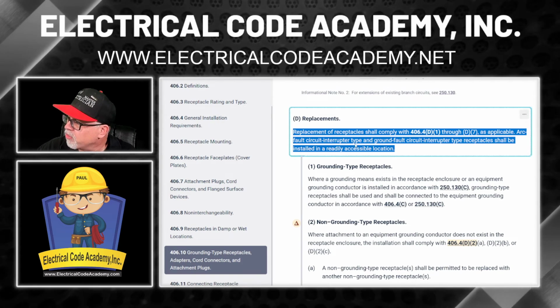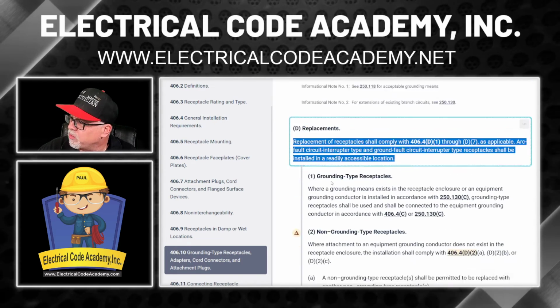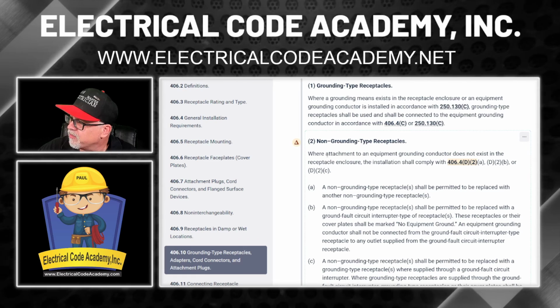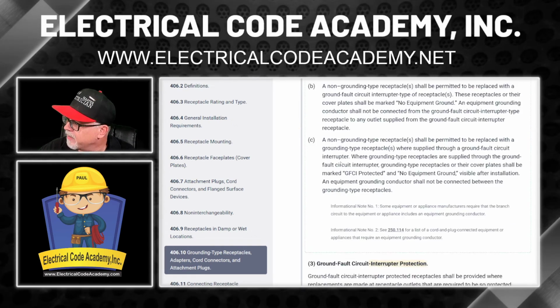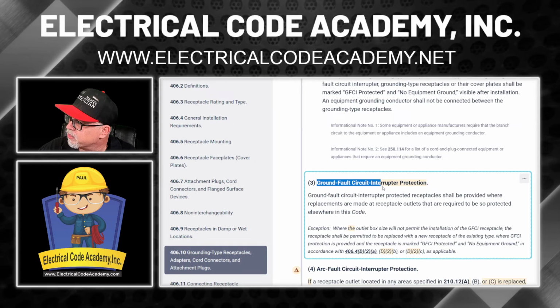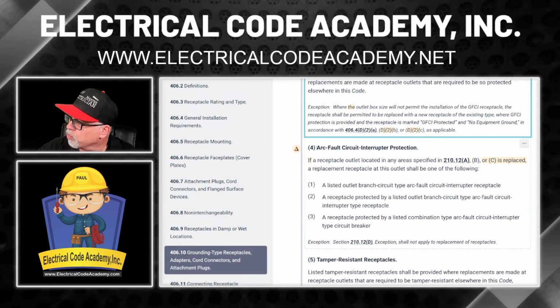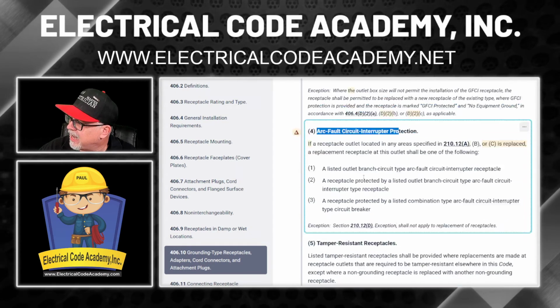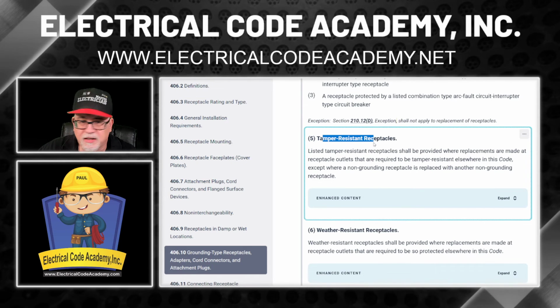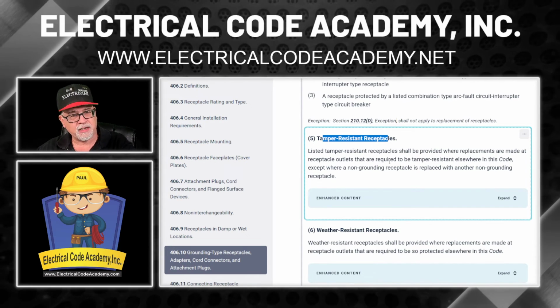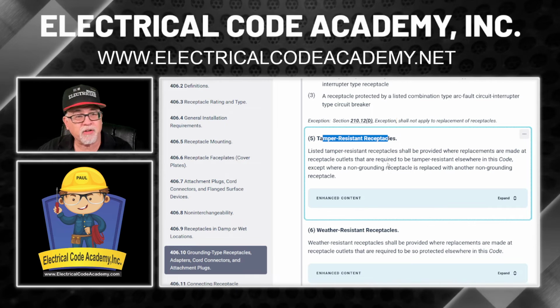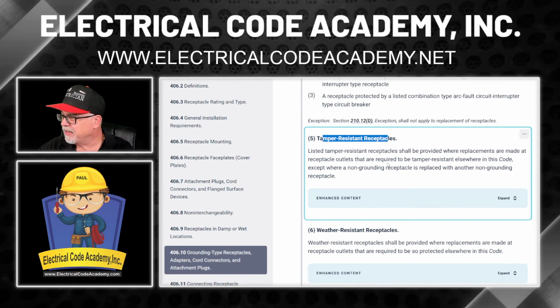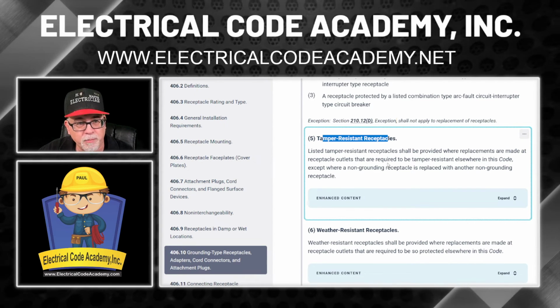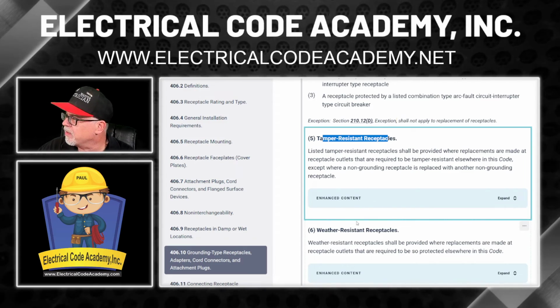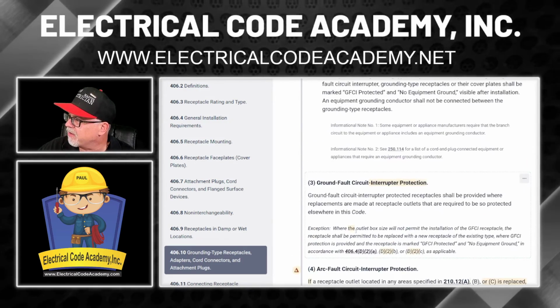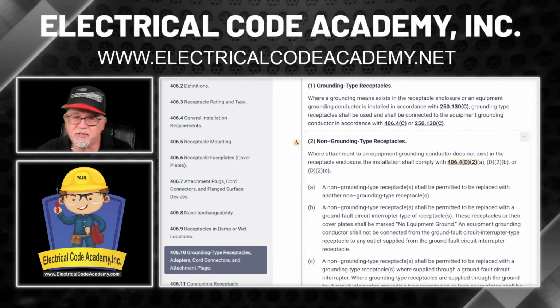Okay, so I will show you real quick. There's D1. We're going to be looking at D2 because this is originally a non-grounded type. But just to show you, there's rules for D3. That's for GFCIs. Here's rules for D4 if you have AFCI. Here's a rule for tamper-resistant. So if you're removing a receptacle in a location that now requires tamper-resistant, then guess what? It's got to be tamper-resistant, okay? You're putting it back, okay? So again, just laying out those rules. All right, so let's deal with his real quick.